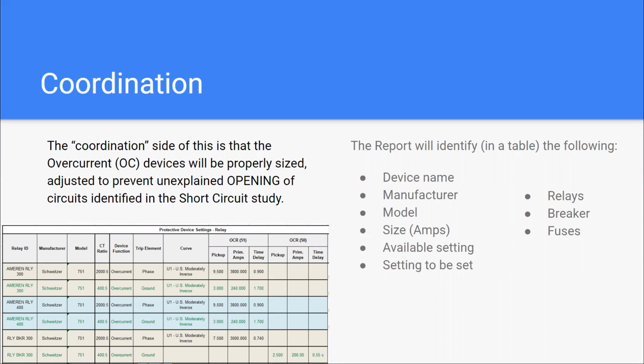to specify all solid state adjustable trip breakers, and you can try to get control over that and achieve perfect coordination, let's call it. But when you're dealing with existing systems, it's almost impossible because you're going to have some device somewhere that you just can't adjust. It's either static trip or it's adjustable, but it only has limited adjustable capabilities, and it's become a big headache.